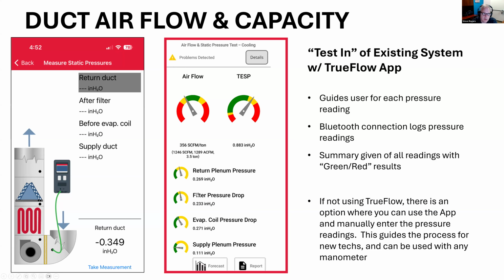So the first thing I've done here is I've just taken the measurements, I've done a testing of the system, and this takes about 10 minutes. Doesn't take a long time. It can easily be done on a sales call and even with a comfort advisor who's not trained as a technician. So that's the measure in process. That can tell me, for the system that's installed here, this system is more like the juice box straw. The pressure's too high and the airflow's too low. That's a good place to start knowing that.